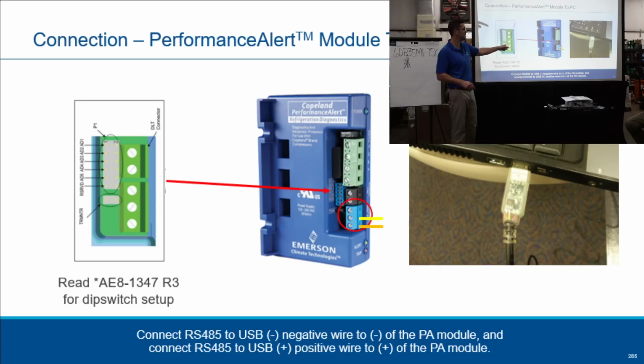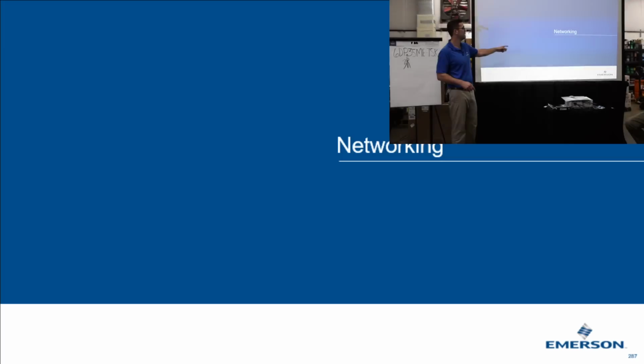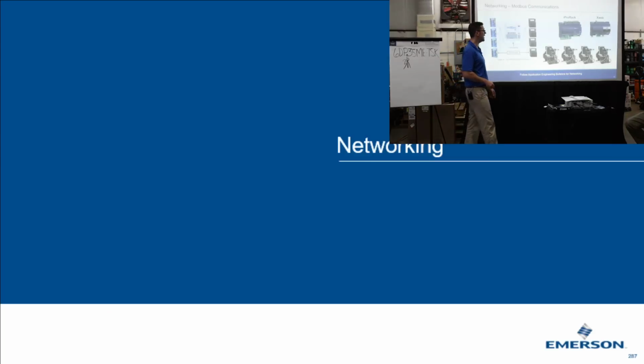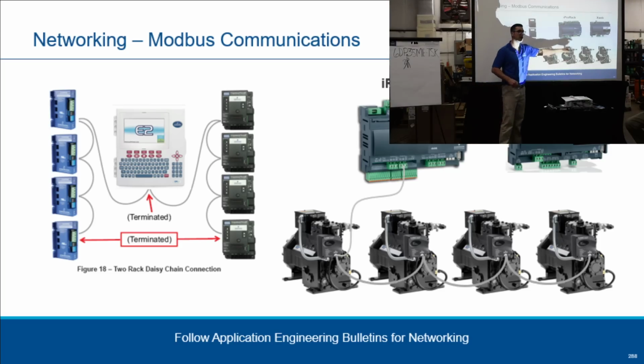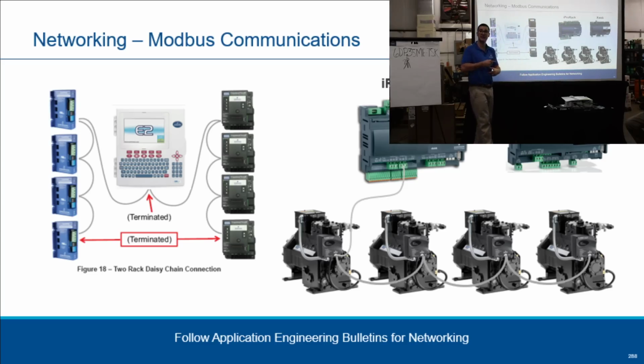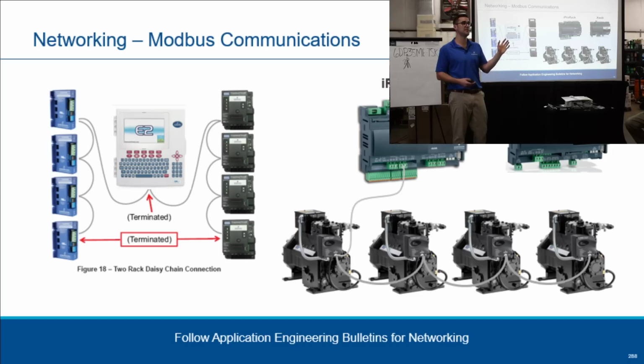Same with this one. Same with this one. Okay. Networking. So you can daisy chain all these back together to a control platform like our iPro Rack or our XWeb and get all that data remotely. Or our E2 platform. Daisy chain them all back and remotely log into these compressors to see why they're running, what's going on with them. When did they trip? Why did they trip? And you don't need a computer to hook up to them. You can read it from the different platforms.